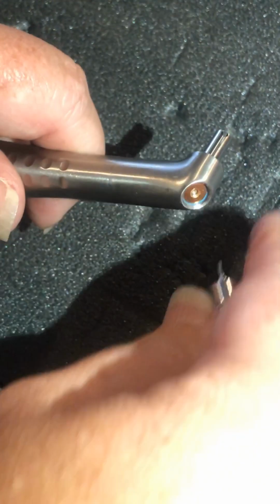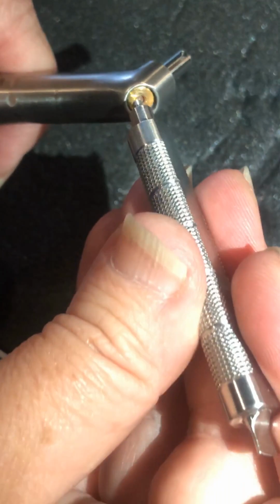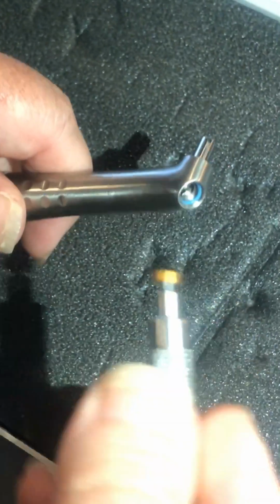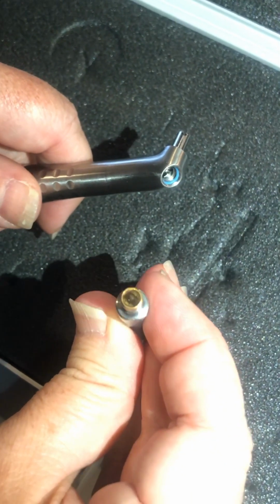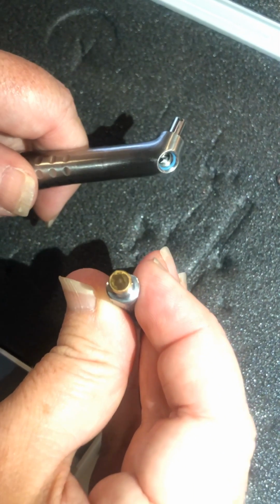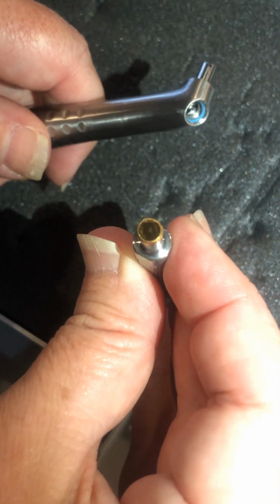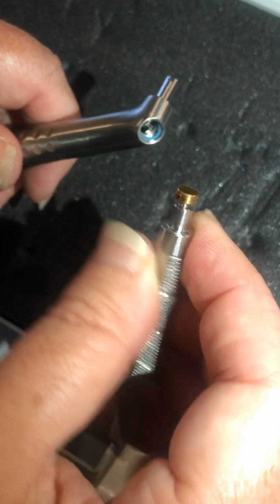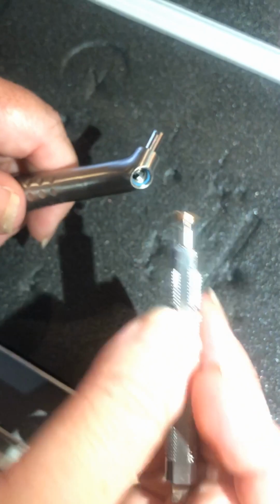Always do this over top of something so that that piece doesn't run away from you. Take the male part, thread it in till you get a good grab, pull straight out, and check that window, or check that mirror, I mean. If there's any debris, just take a Q-tip with 100% acetone or 70% alcohol, let it dry. After you've cleaned it all off, push it back in. You'll feel it kind of seat.